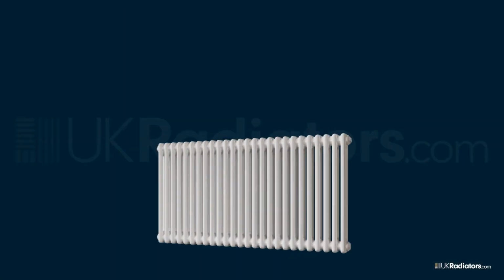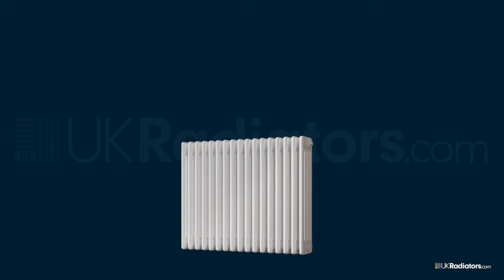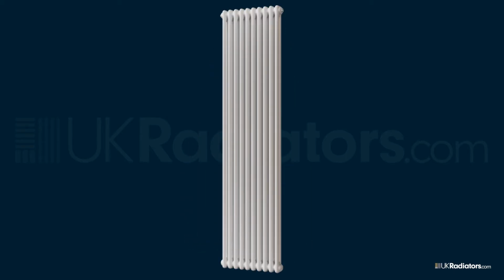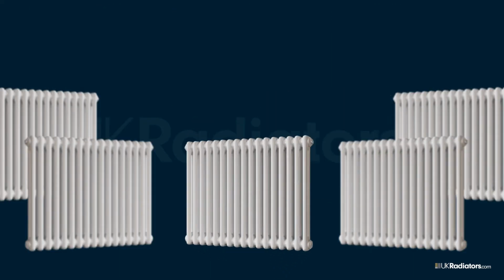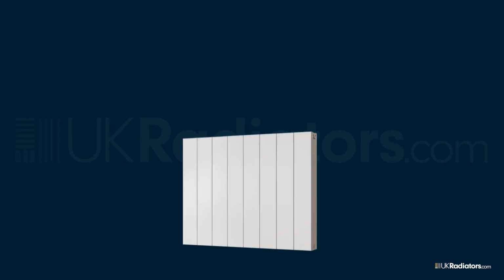Increasing the width of your radiators can sometimes be a challenge, as you may not have the physical space to be able to do this. If that's the case, you can look at adding depth through additional panels or columns, or look at adding radiators with more height, or by looking at vertical radiators. You can also increase the number of radiators in a room to achieve the same goal. You may also be able to find radiators that are the same size as what you have in place, but that are made of a different material like aluminium and still have a higher heat output.